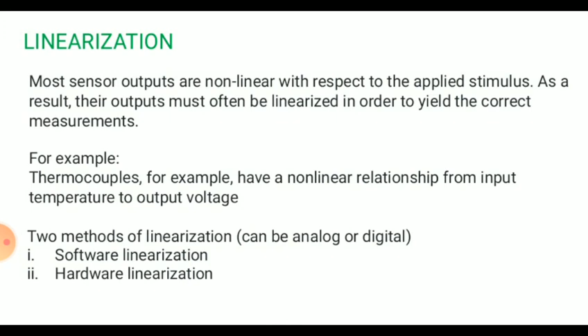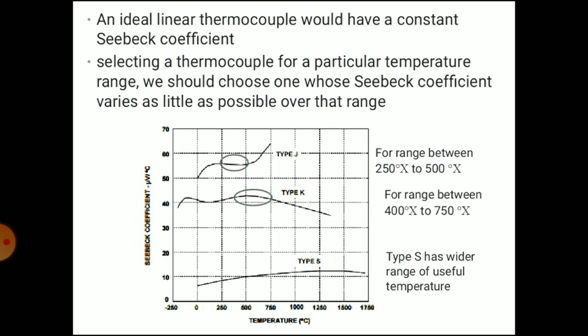The first plot is the plot of voltage versus temperature for three types of thermocouple. The second graph is the plot of nominal Seebeck coefficient versus temperature for three types of thermocouples. An ideal linear thermocouple would have a constant Seebeck coefficient. Selecting the thermocouple for a particular temperature range, we should choose one whose Seebeck coefficient varies as little as possible over that range. So this is regarding the isolation and linearization. Thank you.